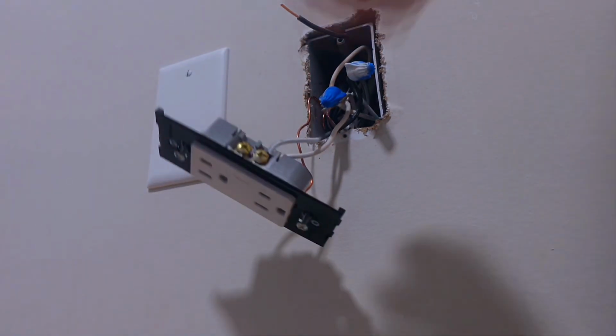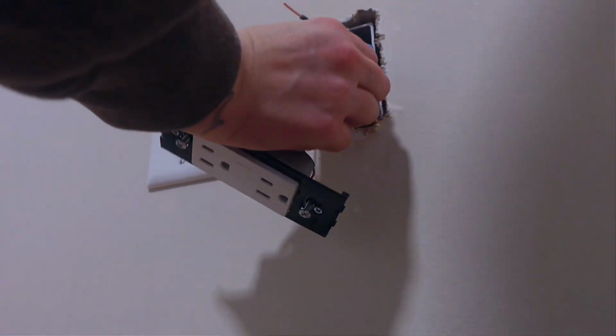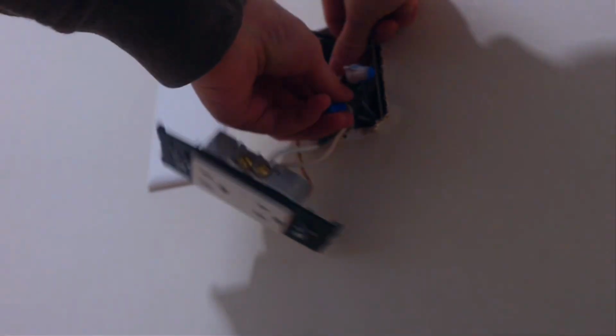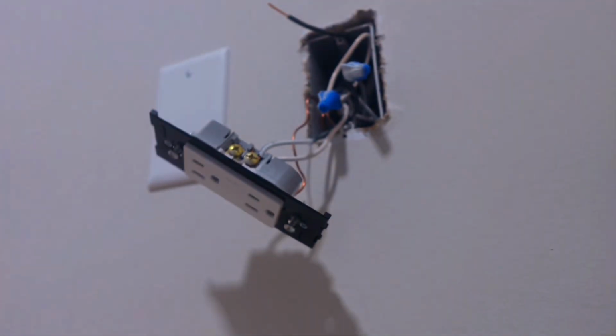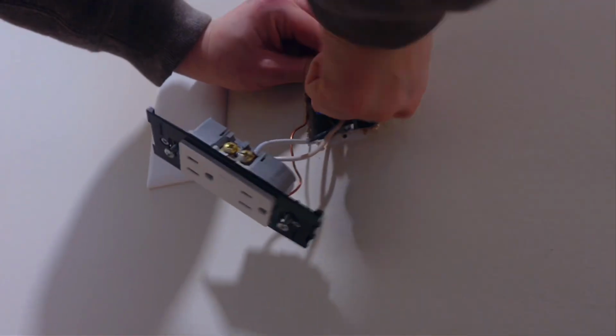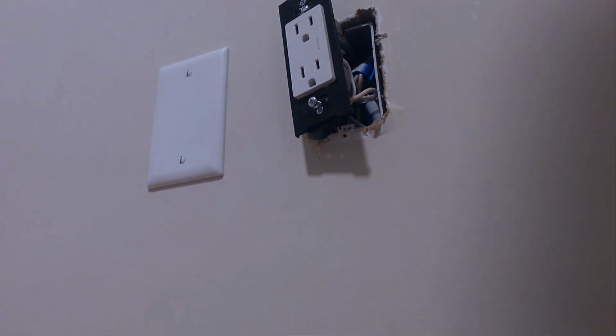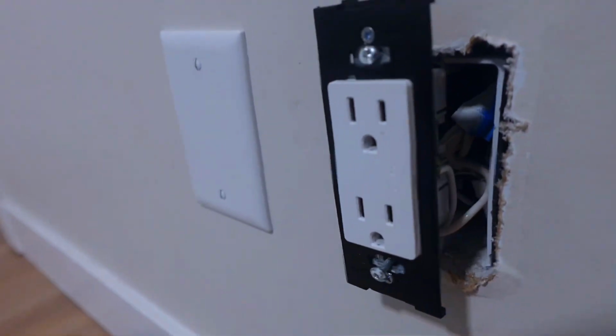When you're securing the wire nut, you wanna make sure that it is nice and tight. You can go ahead and give your wires a pull to confirm that. And the most important thing you should know when you're putting a receptacle on is you do not want this bond wire to touch the hot screw. Otherwise, it will short out on you.